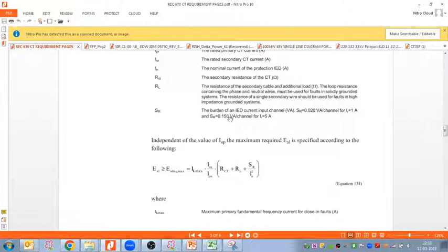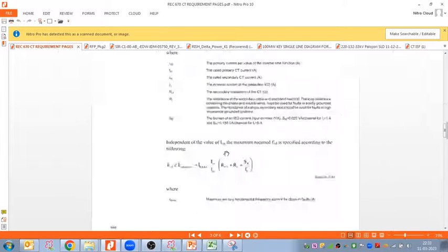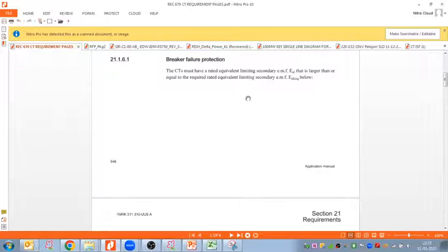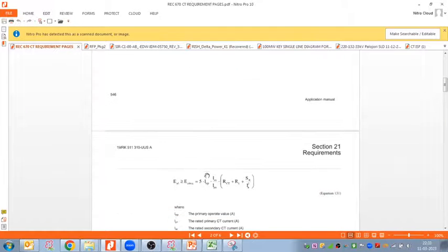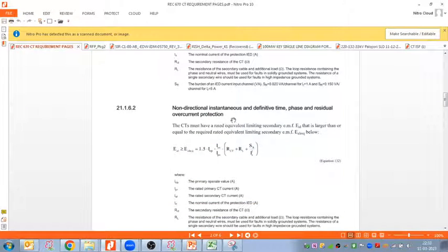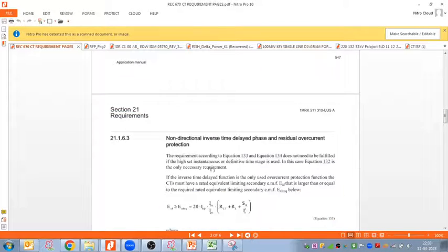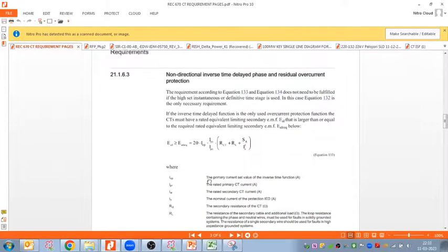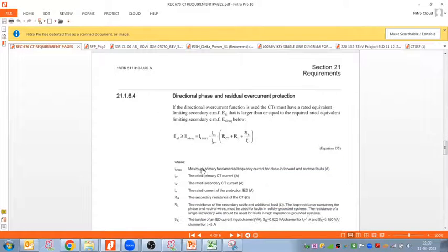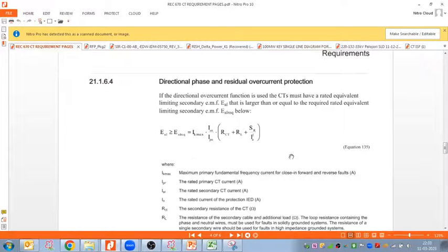Now if you see, the relay function is also changed. So let us see the breaker failure protection. If we are using the breaker failure protection, this is non-directional instantaneous definite time phase protection. So you need to check what kind of protection you are using for this relay, and pick that formula here. For directional phase and residual overcurrent protection, this formula will come. So the formula would change.